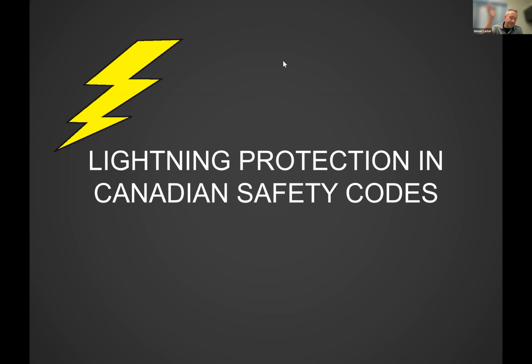Yeah, because with lightning current going through there, the magnetic field moving through so quickly induces a current on the metallic conduit, which could interfere with the lightning current flowing through. So we make sure we are electrically continuous with that conduit top and bottom. That does help.